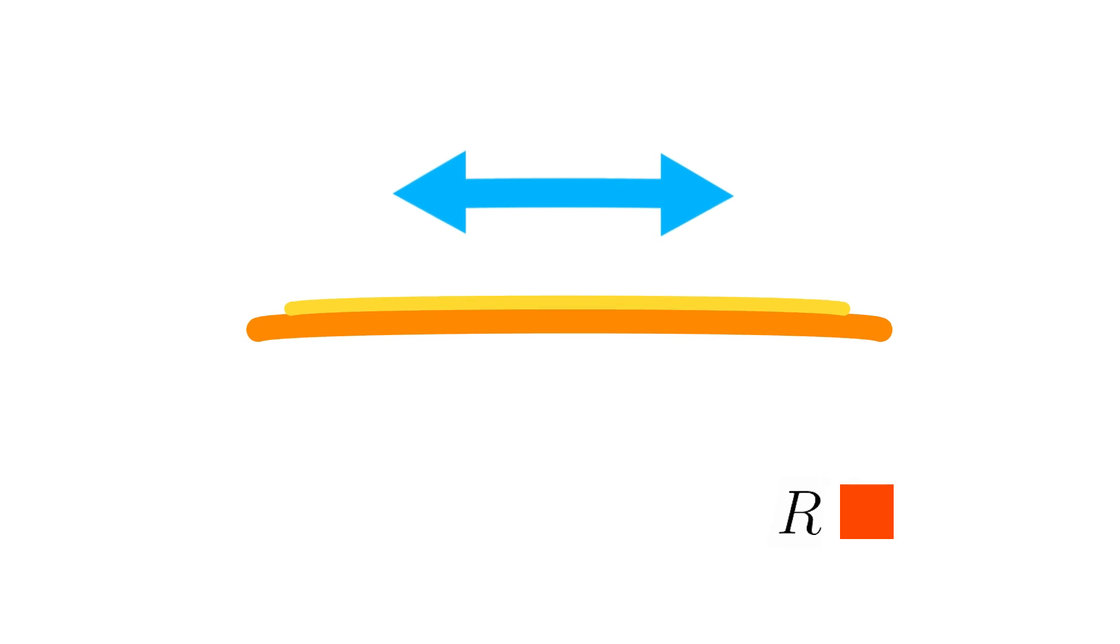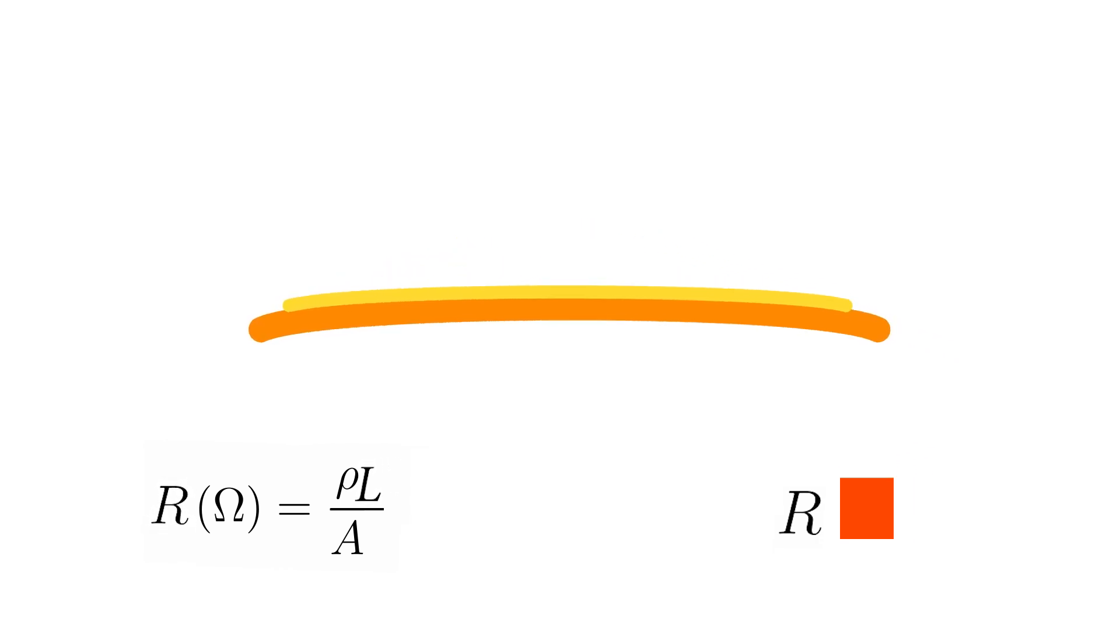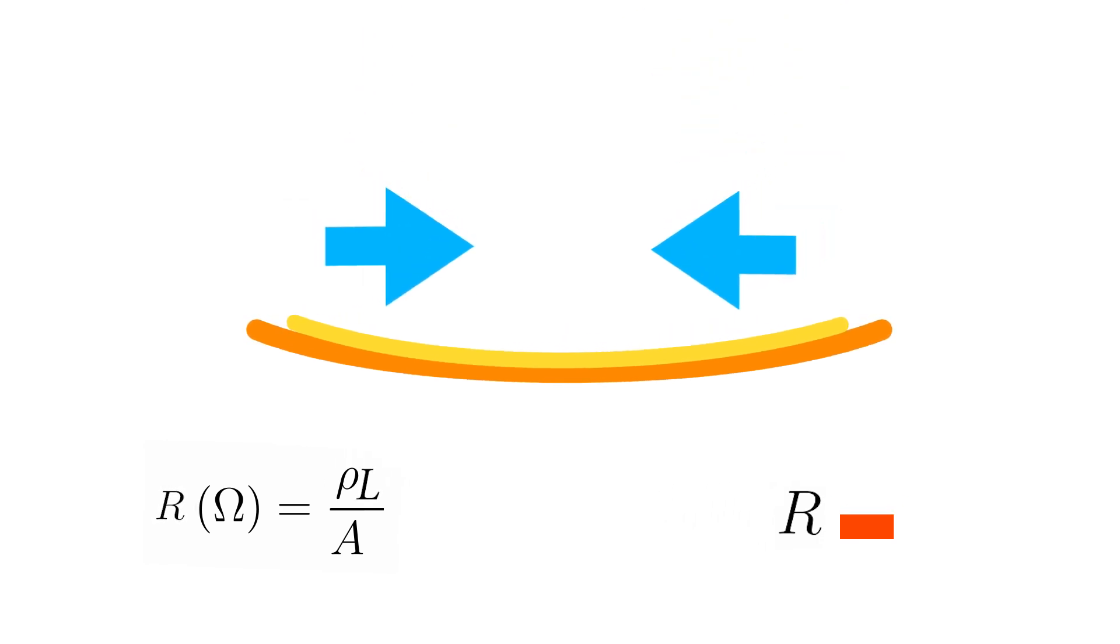These guys have to measure a very small change in physical dimensions. So it's important that we provide enough resistance for it to do its job and allow us to take a measurement. The output voltage will be proportional to the resistance and the change in both will be very, very small. If the strain gauge is bent upward relative to the substrate, the resistive element will elongate and the resistance will increase. If we bend the strain gauge into compression, the resistive element is in contraction and the resistance actually decreases.